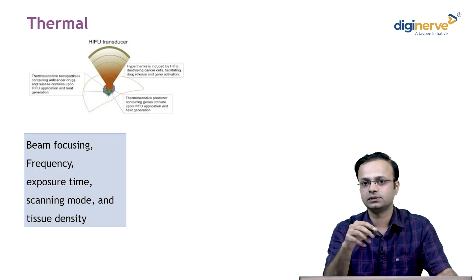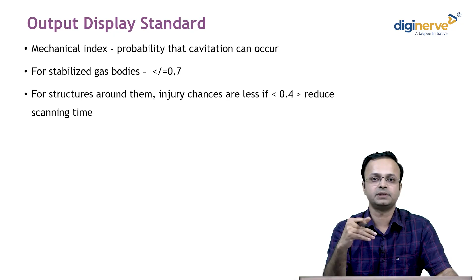Each ultrasound machine has something called ODS, output display standard. It shows the mechanical index and the thermal index. These are not safety values. They are just indices which tell us how much of a risk there is to the tissue being examined. For stabilized gas bodies like the intestine, it should be less than 0.7. If it is less than 0.7, we can continue examination. If the index increases, then it is better to avoid examination in that area for some time.